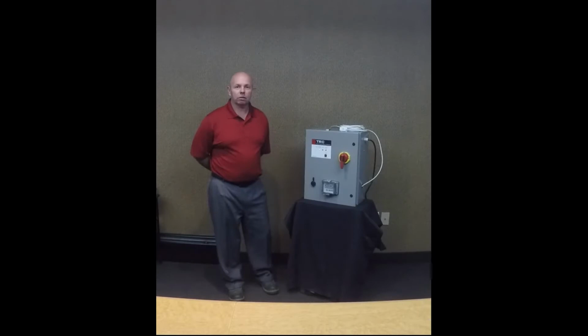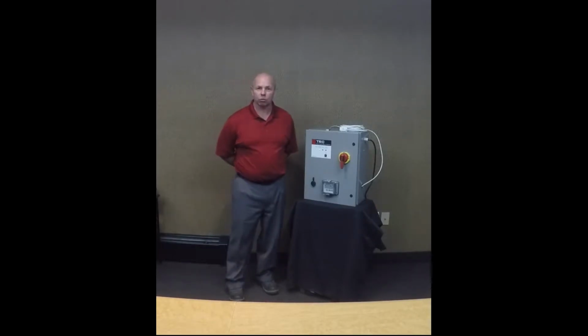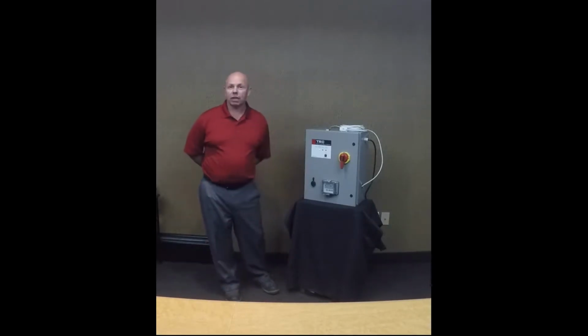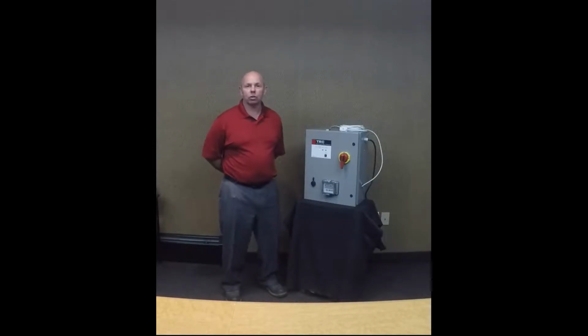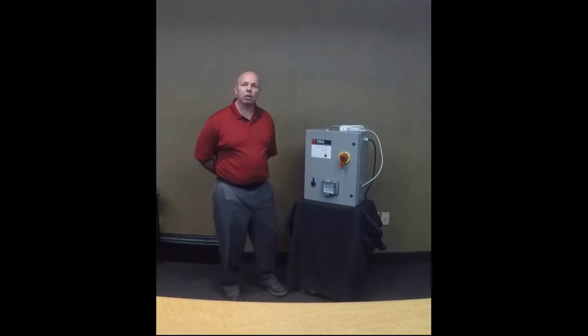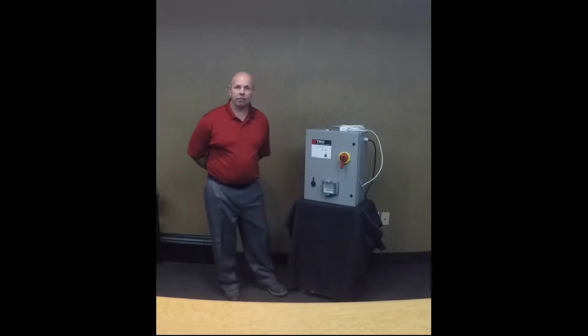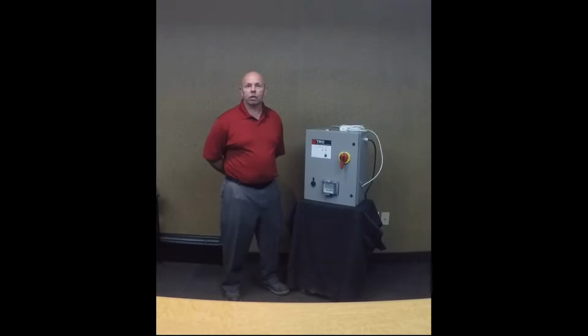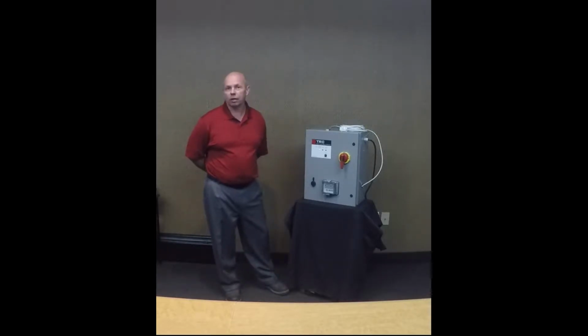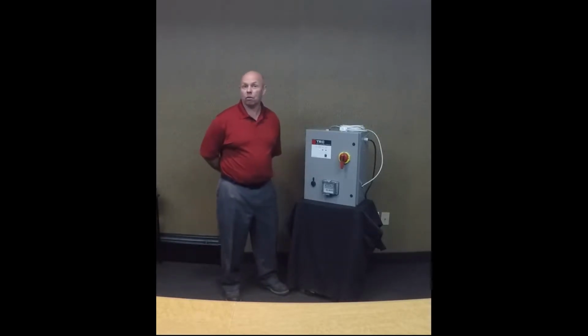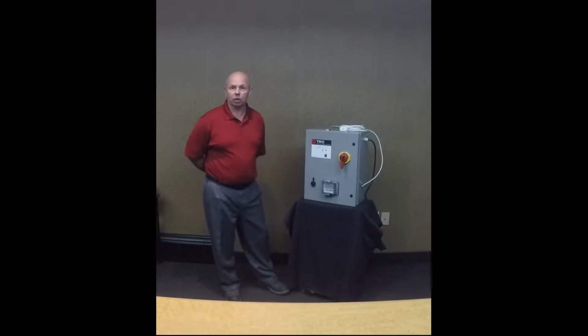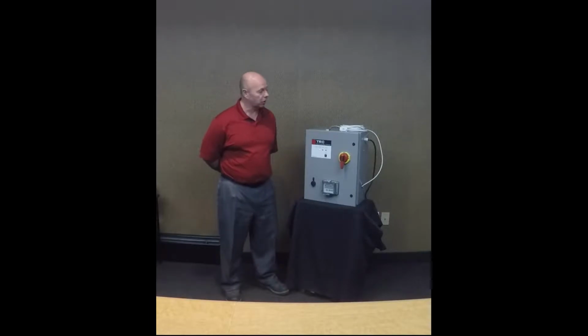Today we're talking about the TRC P1 arc flash relay system. The P1 arc flash relay system is one method to reduce incident energy. This is an approved method under NFPA 70, Article 240.87, which requires arc flash mitigation for any circuit where there is a 1200 amp breaker or more. But this can be used on any system regardless of the breaker size.